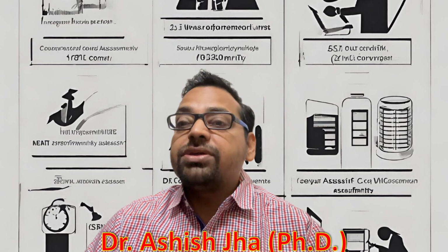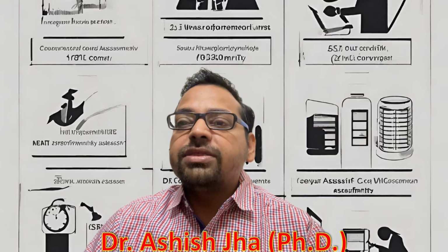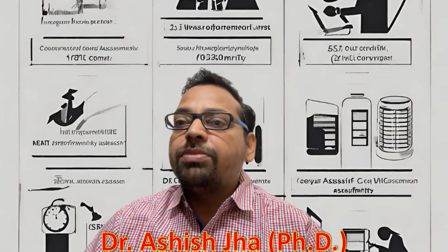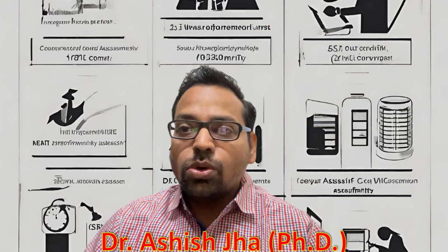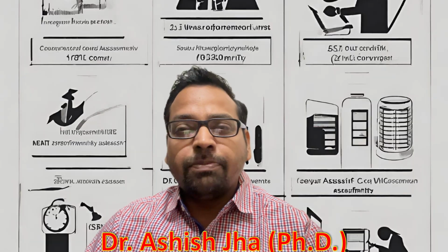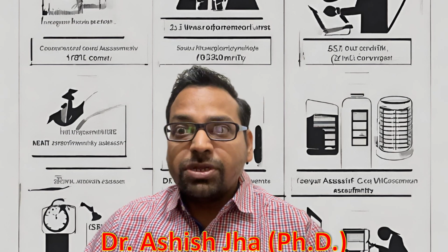That assessment covers each and everything, whether it is clinical data, in vitro data, or in vivo data, whatever data and information they have related to the manufactured medical device. They assess each and everything, and that assessment is called the conformity assessment. Once the manufacturer feels that everything is on the correct path, and the procedures and protocols are followed in a regulated and proper way, only then do they decide to send all these documents and data to the regulatory and authorizing body before getting the medical device into the market.